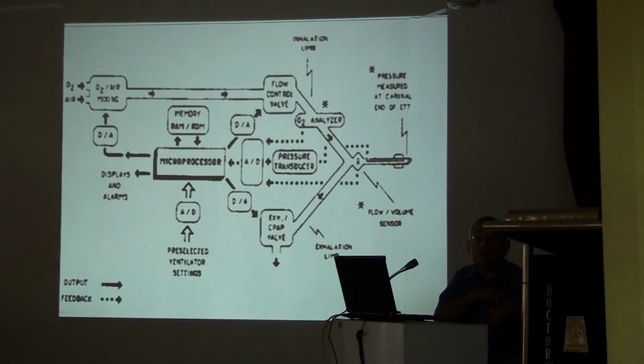Then what happens? There is a sliding valve, like this inspiratory and expiratory valve, that small piston both work together and a flywheel moves. That was the basic principle of a steam engine. So if you mimic the steam engine for this ventilator technology, that is also the same thing. If you have compressed air supplied from the cylinder, if you fit this compressed air and make an engine like a steam engine, that also will work. Without any electricity, without anything, only with the air pressure, the machine works.